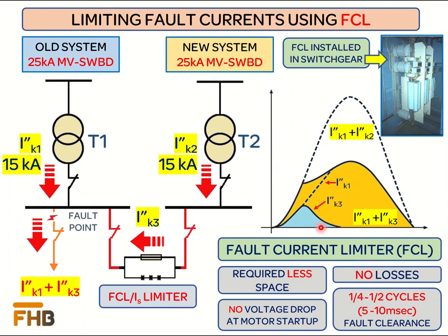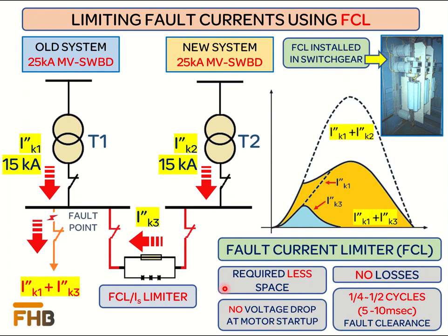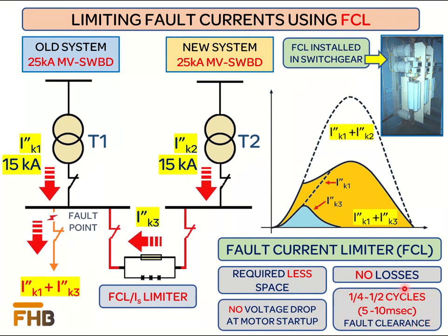The combined value, which is the sum of IK1 and IK3, will remain significantly less than the combined value of IK1 and IK2. FCL brings certain advantages compared to current limiting reactors: it requires less space and can be installed within a switchgear; since the current path is through a copper bar, no losses are introduced by the FCL; there will not be any additional voltage drop at the time of motor startup; and the biggest advantage is the fault clearance time by FCL, which is less than half a cycle.